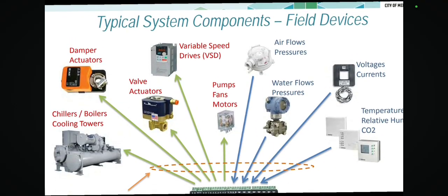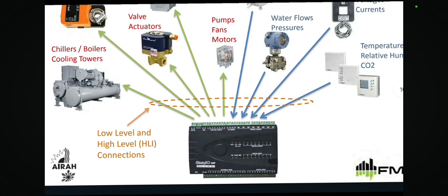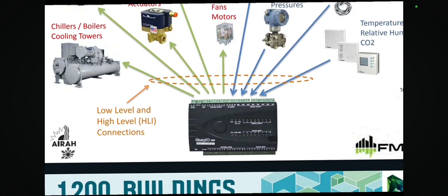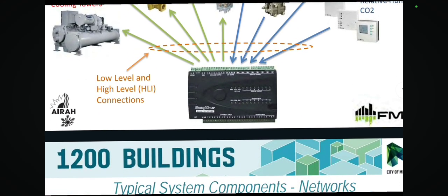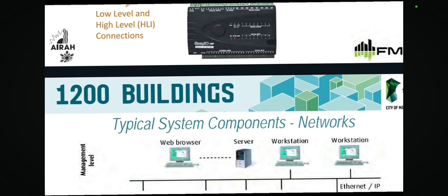Typical system components are field devices like damper actuators, valve actuators, variable speed drives (VSD), air flow and pressure sensors, pumps, fan motors, water flow and pressure sensors, voltage and current sensors, temperature and relative humidity sensors, chillers, boilers, cooling towers, etc. All of these connect to the DDC panel, the BMS panel.